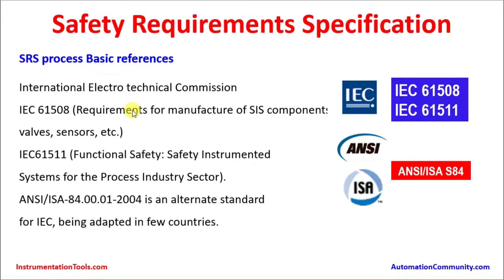IEC 61508 defines the requirements for manufacturers of SIS components such as valves and sensors. IEC 61511 covers safety instrumented systems for the process industry sector — specifically how they need to be installed, commissioned, validated, proof tested at regular intervals, and maintained. ANSI/ISA 84 is an equivalent standard to IEC 61511, adapted in countries such as the Americas.